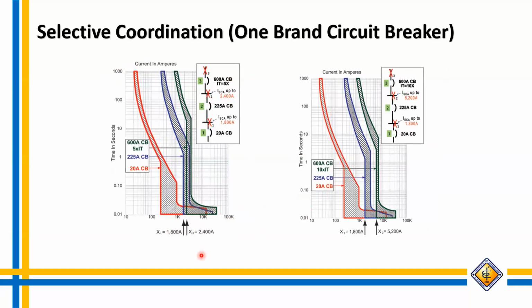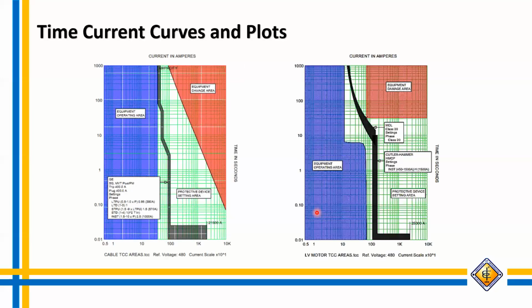So for this one, for example, I have a fault less than 1,800. Definitely the system is selectively coordinated if the fault is around 1,800 and below. But if our fault is 1,800 and above, definitely the red curve will trip simultaneously with the blue. So that's the analysis there. Okay? Later I will show a sample so you can better appreciate the curve.